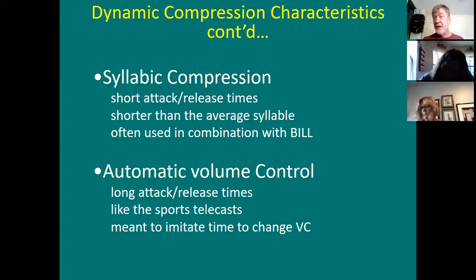Syllabic detection was big on Bill. So Oticon used syllabic detection for the low frequencies. And the reason why is because lows mask highs better than highs mask lows. Remember that? That was one of the intellectual reasons for using Bill.